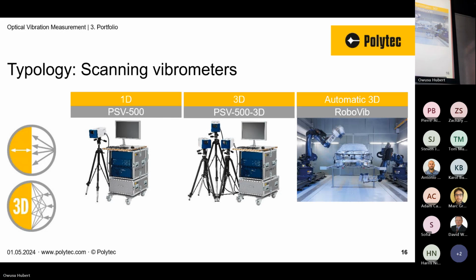All right. There was a study, I forgot the name of it, and they used a probe, I forgot the name of the probe, which measures from DC, from 0 upwards, and we also use our vibrometer. What we don't do is take account of the surface movement of the object. We measure from where it points at it. So even if your object is maybe curved that way, wherever we point at, that's what we are getting. So it's not a matter of how much your surface is curved or bent. We can point the laser on it, receive light back to the sensor head, good to go. So it doesn't matter what the surface is. Okay. Yeah, the surface doesn't matter.